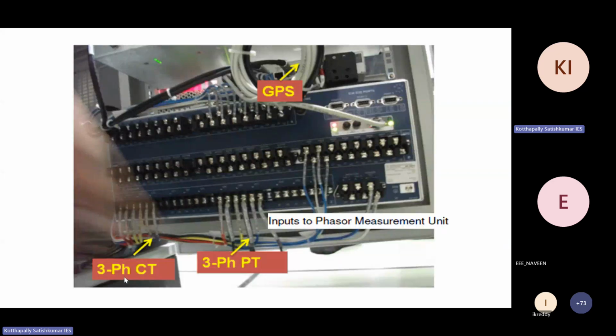For example, this is the back side of a PMU. You connect three-phase CT, taking three inputs, and from the PT you also take three inputs — three-phase CT and three-phase VT. Each set is taken as one channel, meaning one channel has three pins, either for CT or PT.